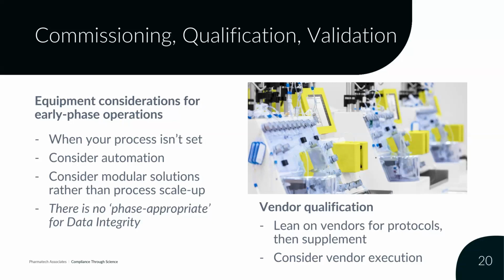My user, my process scientist, tells me they want this machine. Then what I have to do is say, well, they know what they need. They want this machine, right? Then what you do is you look to what the manufacturer says that machine's going to do, and you make sure you verify, you qualify that the machine actually does those things. Pull the critical GMP functionality out of the manufacturer's spec sheet, and call that the user requirement specification.